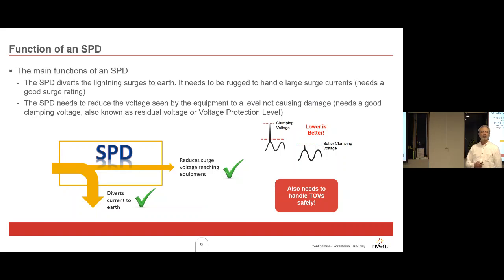The main function of a surge diverter is to divert the lightning surge to earth. It needs to be rugged and to handle large surge currents, and so it needs a good surge rating. It needs to reduce the voltage seen by the equipment to a level that doesn't cause damage. No surge diverter is perfect enough to stop any of the surge coming through, so it's how much of that surge goes through that's the thing that we typically look at.